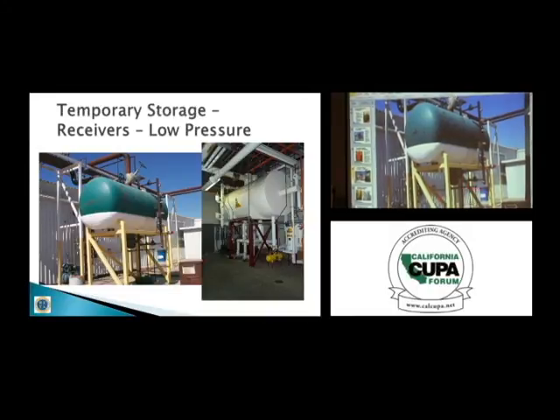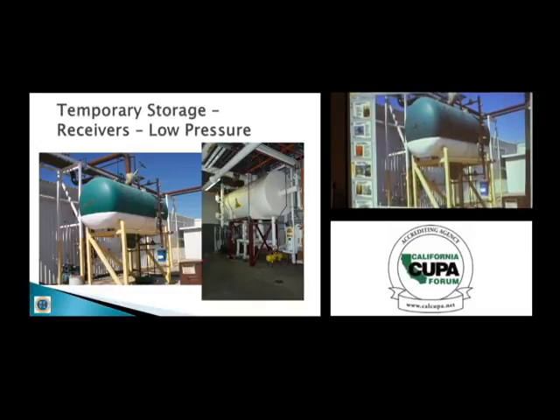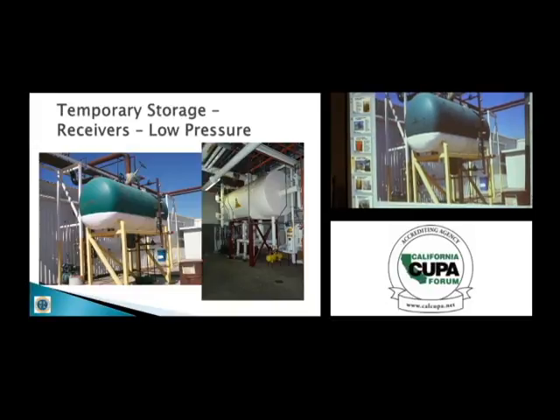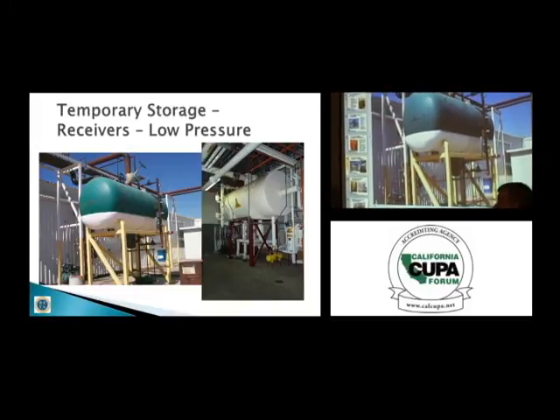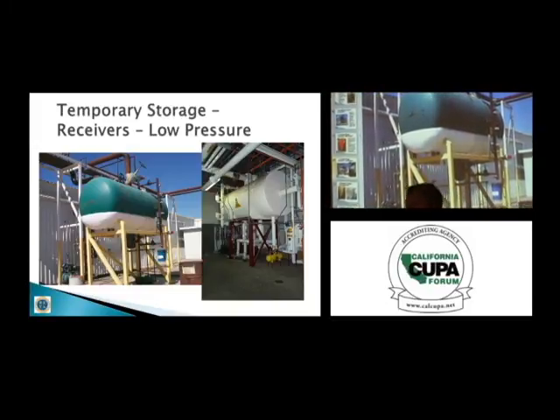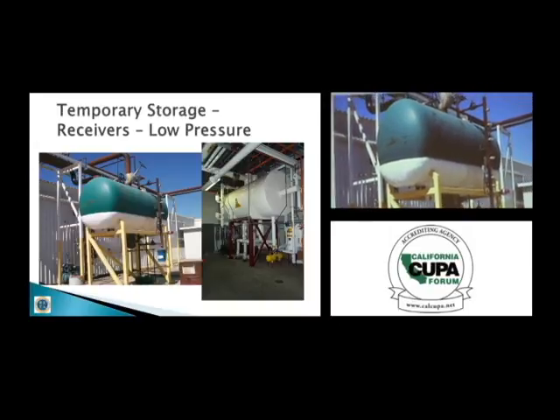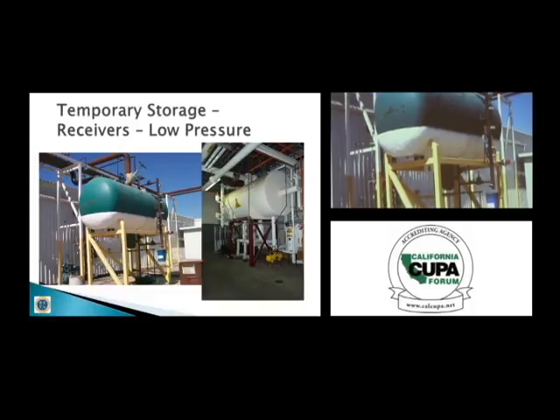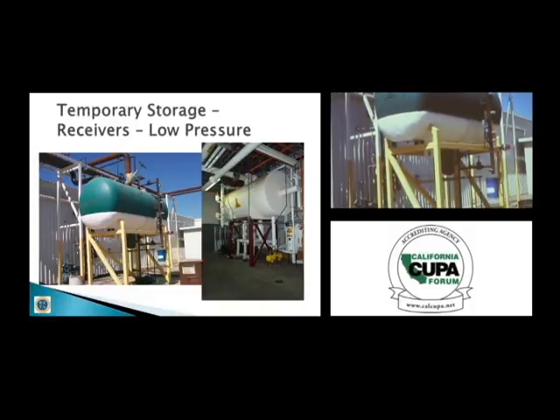Yeah, now, they got a 55-gallon drum of oil there. They've been draining the oil. The oil is hanging on a 1/4-inch pipe nipple that's got a gauge valve, and that's one place where they've been draining the oil out of this float column. And they're leaving it there. So, 5 gallons of oil weighs, 50 pounds? Hanging on a 1/4-inch pipe nipple, for God's sake. A good example of a bad way to operate.